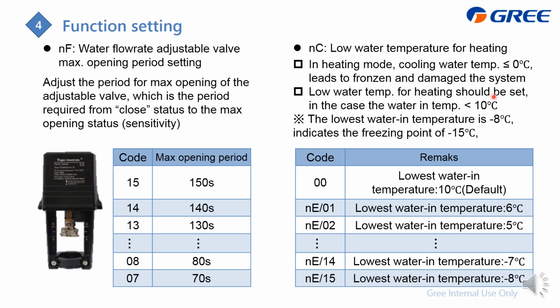And if you would like a lower water in temperature, besides you need to add some antifreeze into the water system, and also on the setting of this one, NC, you also need to change it. The lowest limit of the water in is -8, and with antifreeze, indicating the freezing point, it can be -15. And here are the different codes according to different water in temperatures. Our default setting is 10, so it will be 0, 0.